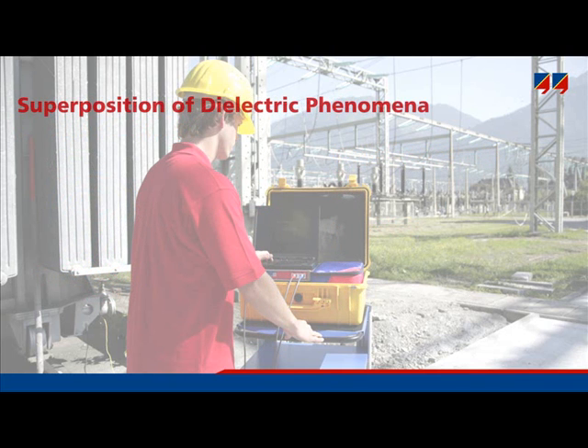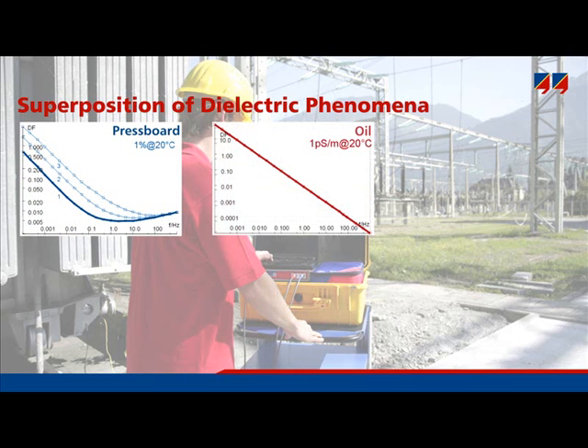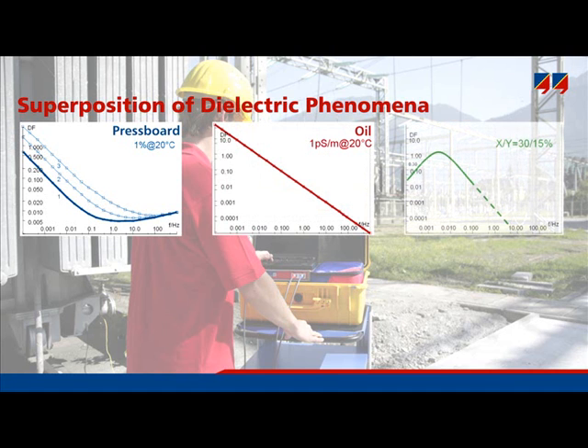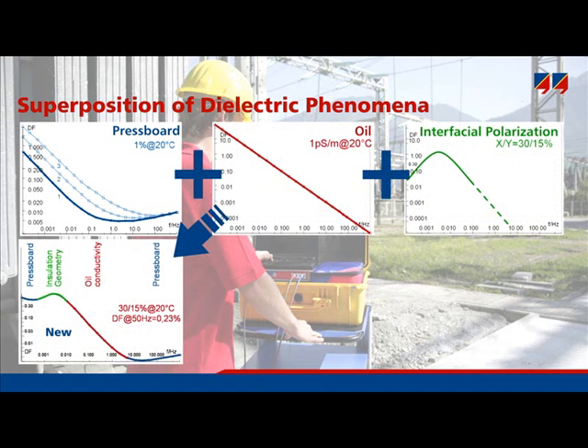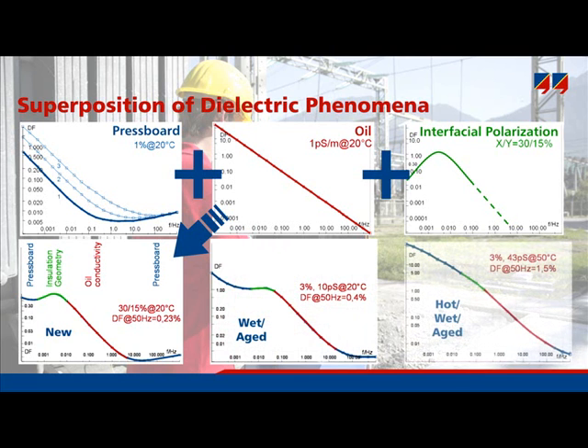This slide shows how these different physical properties are superimposed onto the dielectric response which is measured. The diagrams display dissipation factor over a wide frequency range down to 1 mHz. Only the pressboard exhibits a particular shape of dissipation factor against frequency, while only the dissipation factor of oil follows a straight line. Since the insulation consists of oil and pressboard, the superposition of both together with interfacial polarization gives this typical S-shape of dissipation factor against frequency. An increasing water content or higher degree of aging byproducts will cause the curve to shift towards higher frequencies, though the shapes remain very similar. Temperature — shown here at 50 degrees Celsius — will additionally shift the curve to the right-hand side and also increase the losses.